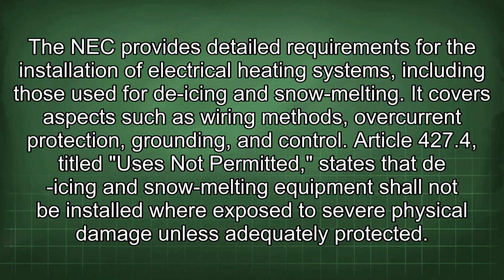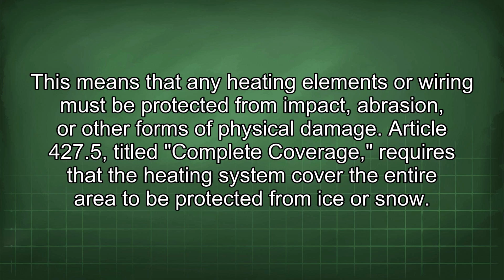The NEC provides detailed requirements for the installation of electrical heating systems, including those used for de-icing and snow melting. It covers aspects such as wiring methods, overcurrent protection, grounding, and control. Article 427.4, titled Uses Not Permitted, states that de-icing and snow melting equipment shall not be installed where exposed to severe physical damage unless adequately protected. This means that any heating elements or wiring must be protected from impact, abrasion, or other forms of physical damage.